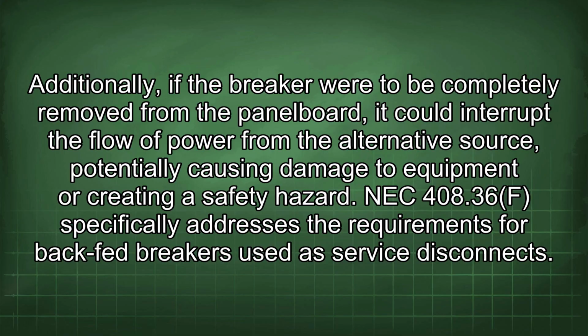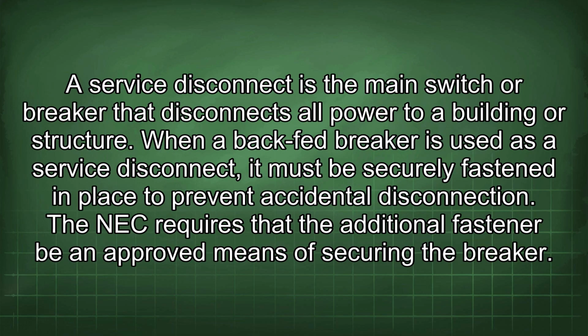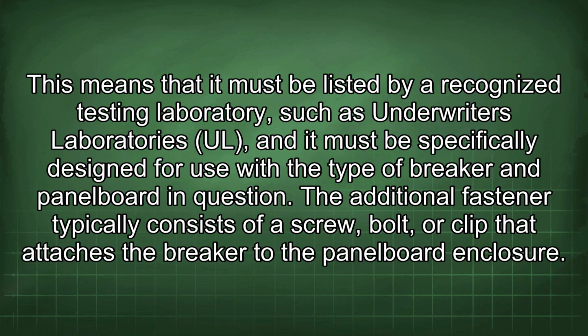NEC 408.36 specifically addresses the requirements for backfed breakers used as service disconnects. A service disconnect is the main switch or breaker that disconnects all power to a building or structure. When a backfed breaker is used as a service disconnect, it must be securely fastened in place to prevent accidental disconnection. The NEC requires that the additional fastener be an approved means of securing the breaker. This means that it must be listed by a recognized testing laboratory, such as Underwriters Laboratories UL, and it must be specifically designed for use with the type of breaker and panel board in question.